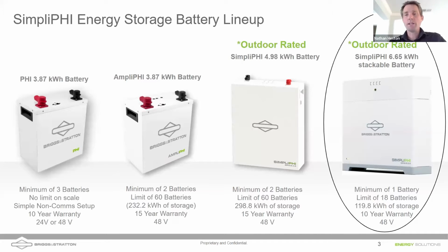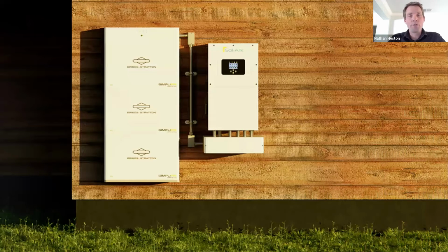But we're really going to be highlighting today the battery on the right. This is the latest battery from SimpliPhi Power, Briggs & Stratton. It's a stackable battery, and this stackable battery can be either floor or wall mounted. We've got higher output, and again, it's perfectly suited for the Sol-Ark 15K. So here's what that battery looks like on a wall with a Sol-Ark 15K inverter, outdoor rated battery, outdoor rated inverter, a very nice pairing, and we'll talk about all of the advantages to those Sol-Ark 15K inverters, which is what's making them so popular.